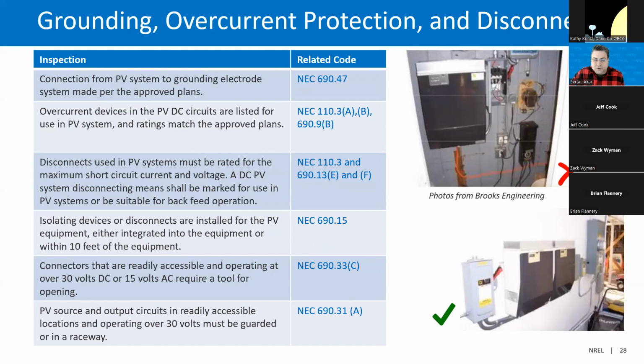Next thing is the grounding, overcurrent protection and disconnects. The inspector should check that the connection from the PV system to the grounding electrode system is made per approved plan, and OCPDs are listed for use in PV systems, and ratings must match the approved plan. Disconnects used in PV systems must be rated for maximum short circuit current and voltage. Isolating devices or disconnects must be installed for the PV equipment, either integrated into the equipment or within 10 feet of the equipment. Connectors that are readily accessible and operating at over 30 volts DC or 15 volts AC require a tool for opening, and PV source and output circuits in readily accessible locations operating over 30 volts must be guarded or in a raceway.